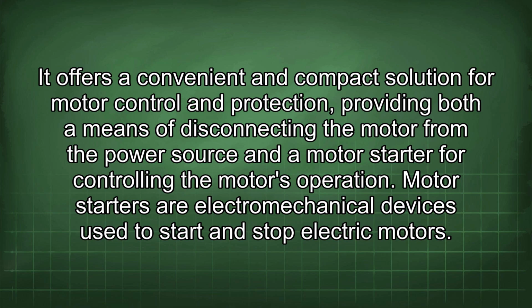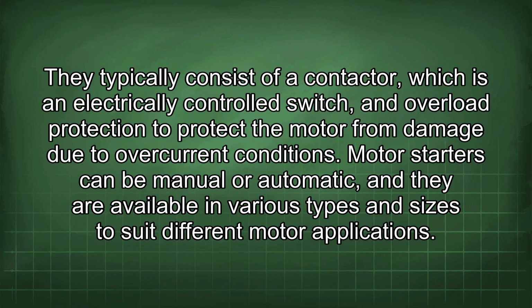Motor starters are electromechanical devices used to start and stop electric motors. They typically consist of a contactor, which is an electrically controlled switch, and overload protection to protect the motor from damage due to overcurrent conditions. Motor starters can be manual or automatic, and they are available in various types and sizes to suit different motor applications.